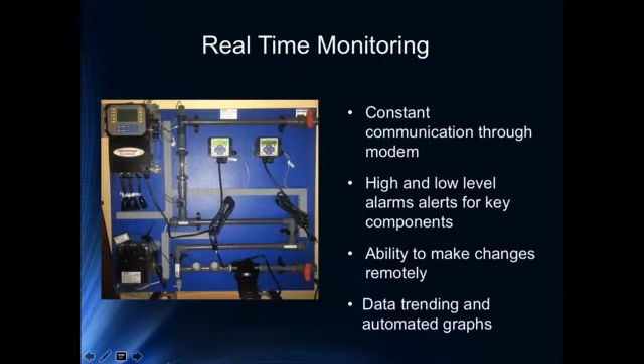Real-time monitoring, again, we have a tremendous amount of mechanical equipment that's operating in a cooling tower system. We've got solenoid valves that stick open and closed all the time. That just happens. Blowdown valves. We have makeup water meters that sometimes stick. There's a lot of different things that can happen, and unfortunately, a lot of times it takes somebody walking by the unit to notice that it's occurred, or somebody to happen to be running a test and notice that it's occurred. So we take advantage of real-time monitoring, where our controllers are connected via modem to the cloud.